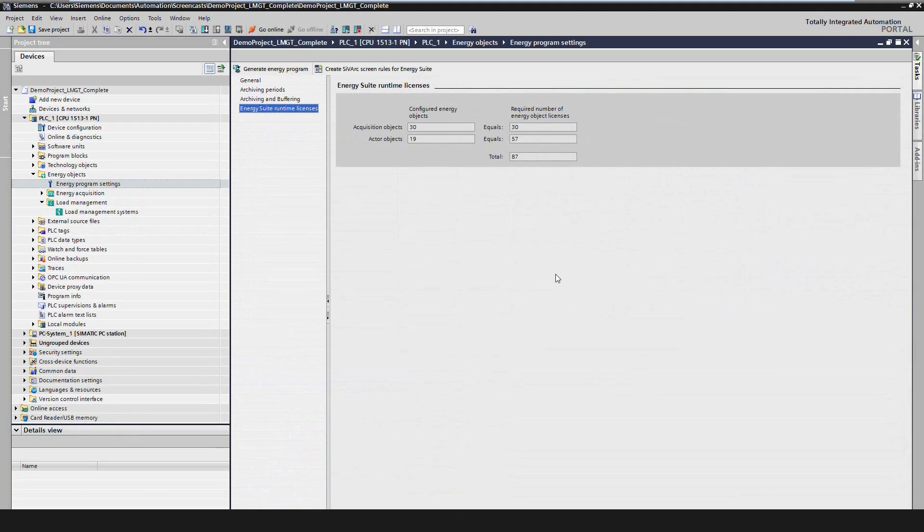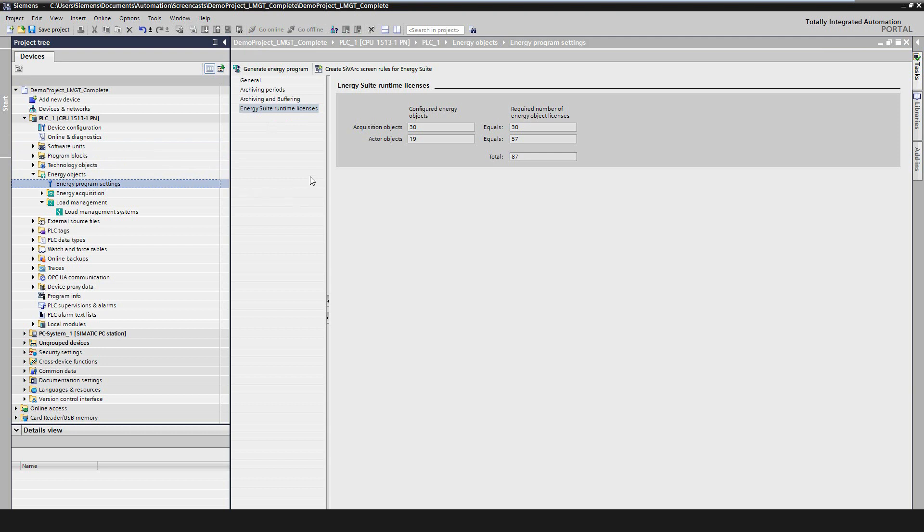Before generating the load management program, the correct number of runtime licenses for the objects must be configured. The at least necessary count can be looked up in a new screen in the energy program settings, where the user gets an overview of the configured number of acquisition objects and actors. The cost for one actor will be three energy object licenses. The acquisition objects will still cost one license.